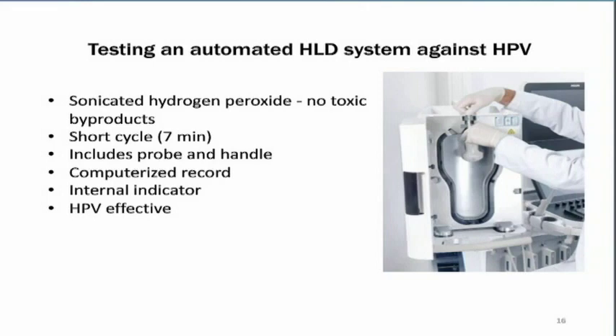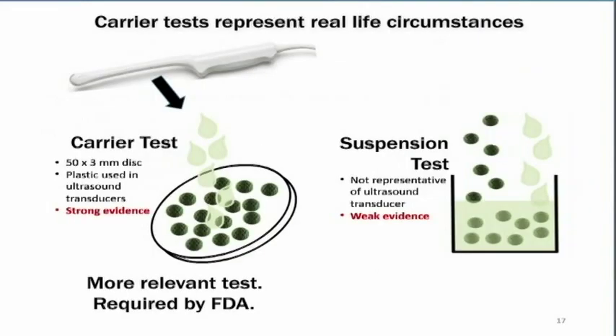Then, with this result, we showed that none of these common disinfectants were able to kill HPV, even ones that have been called high-level disinfectants. So we decided to test an automated high-level disinfectant system against HPV. This system uses sonicated hydrogen peroxide, so there's no toxic byproducts. It has a short cycle time of 7 minutes. It includes both the probe and the handle. It gives you a computerized record. It has an internal indicator, and we found it to be HPV effective.